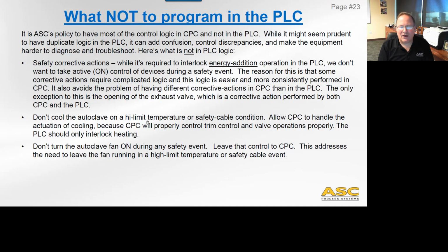The other step is don't cool the autoclave on high temperature limit or safety cable condition. So no active cooling from the PLC perspective. Allow CPC to handle all of that, the actuation of the cooling, because CPC is going to handle trim cooling properly. And when you're at an elevated temperature and you have multiple trim coils and all this other stuff, it gets very complicated if you have to do that in your PLC logic as well as in CPC. So the only thing PLC is going to do in the case of temperature is interlock heating, and that's it.